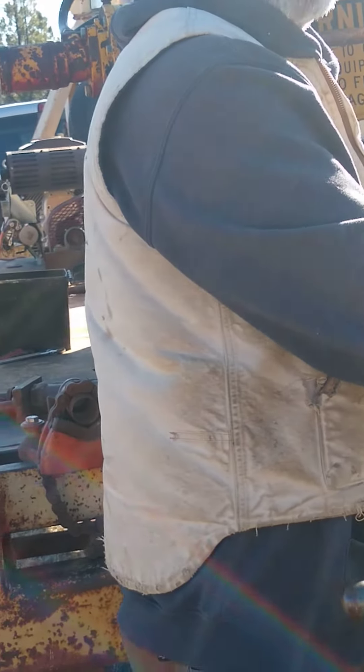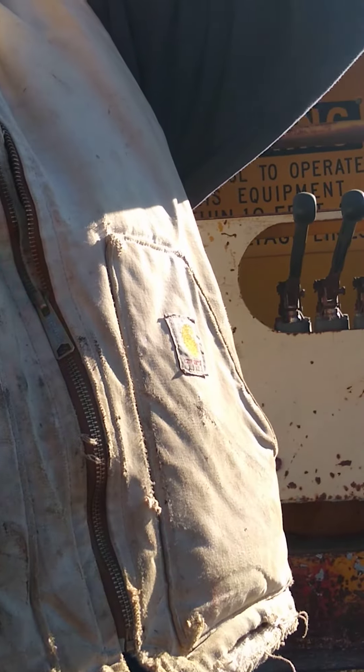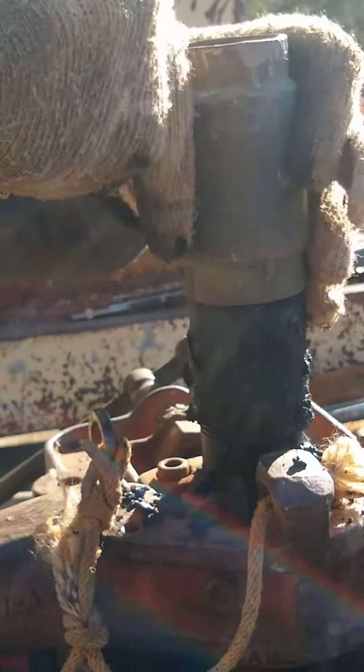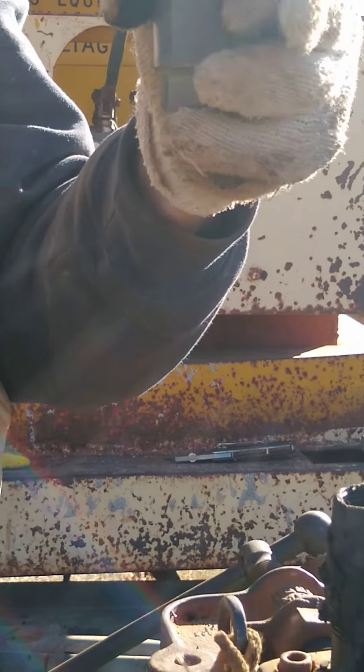We have no water in this plant pipe. There should be check valves — there should be at least two check valves in this line, because that's a lot of water pressure sitting on top of that pump. If these are going and that check valve's bad on top of the pump — this is the pump — that just adds pressure. It'll turn the pump backwards.